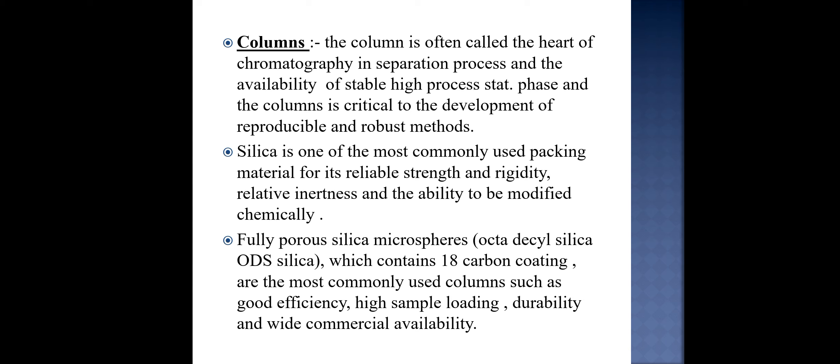Next we will discuss about the column. As we know that column is often called the heart of chromatography because it is the main component in which the sample can be separated. Silica is used. Silica is one of the most commonly used packing material for its reliable strength and rigidity, relative inertness and the ability to be modified chemically. In the stationary phase, the column is critical to development of the reproducible and robust method. Fully porous silica microspheres are also used in which it includes octadecyl silica which is also known as ODS silica which contains 18 carbon coating which is the most commonly used column because of its good efficiency, high sample loading, durability and wide commercial availability. This is the main point used in HPLC is ODS silica. Octadecyl silica is used in which 18 carbon atoms, 18 hydrocarbons are composed.